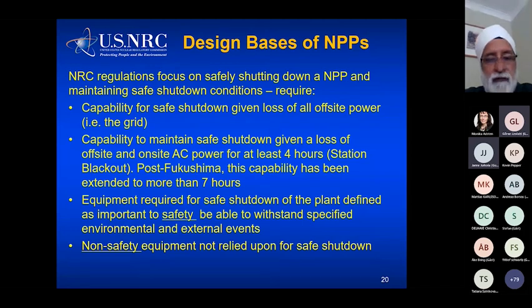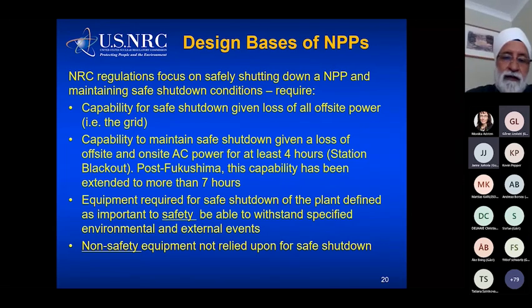We also know that the equipment required for safe shutdown of the plant is usually not connected, and that's important. And you should be able to withstand the external event. And again, we do not rely on non-safety equipment that could be exposed to the EMP.